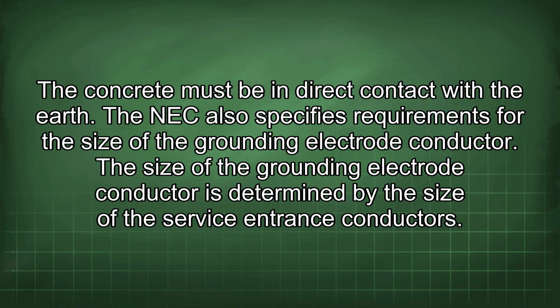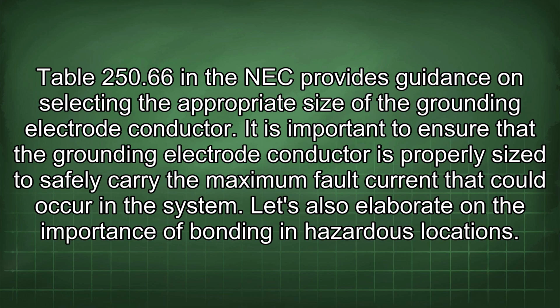The NEC also specifies requirements for the size of the grounding electrode conductor. The size of the grounding electrode conductor is determined by the size of the service entrance conductors. Table 250.66 in the NEC provides guidance on selecting the appropriate size of the grounding electrode conductor. It is important to ensure that the grounding electrode conductor is properly sized to safely carry the maximum fault current that could occur in the system.